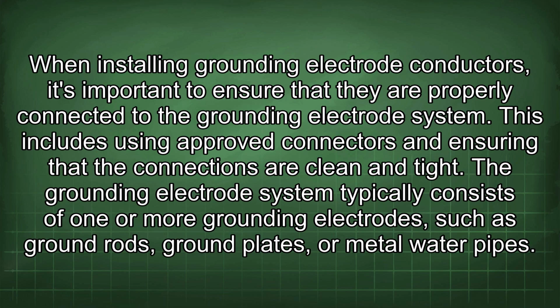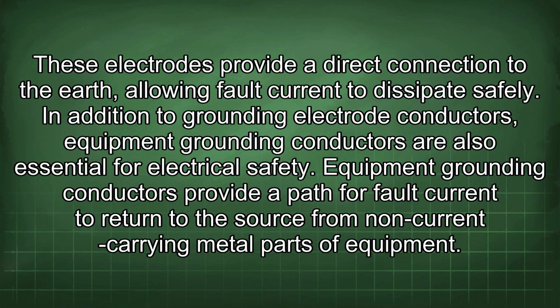When installing grounding electrode conductors, it's important to ensure that they are properly connected to the grounding electrode system. This includes using approved connectors and ensuring that the connections are clean and tight. The grounding electrode system typically consists of one or more grounding electrodes, such as ground rods, ground plates, or metal water pipes. These electrodes provide a direct connection to the earth, allowing fault current to dissipate safely.